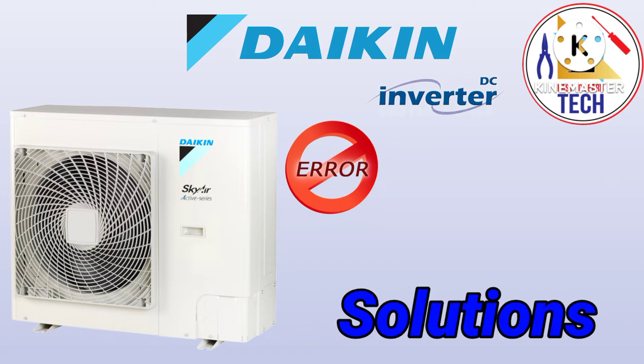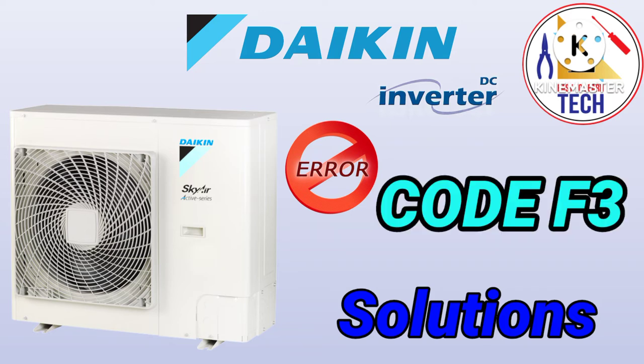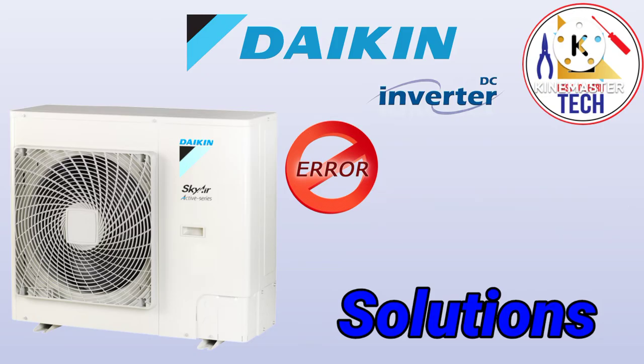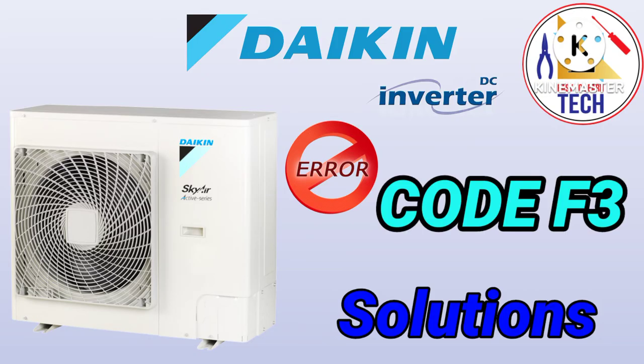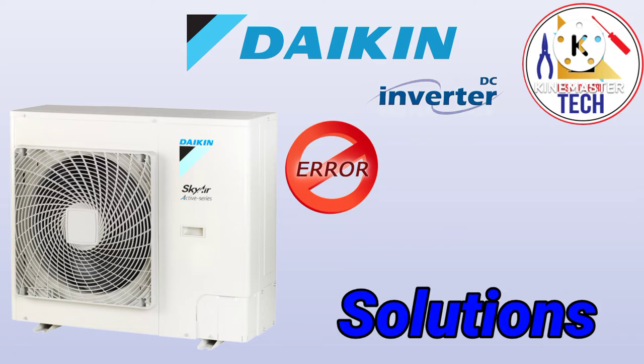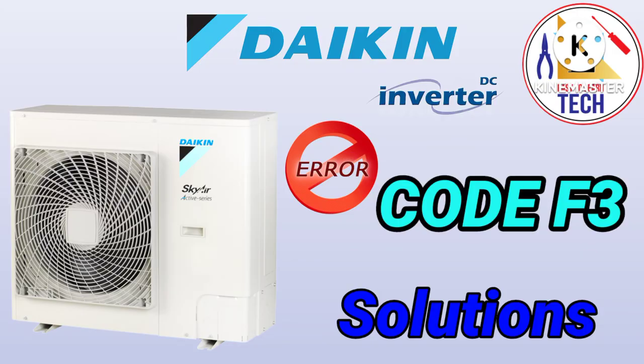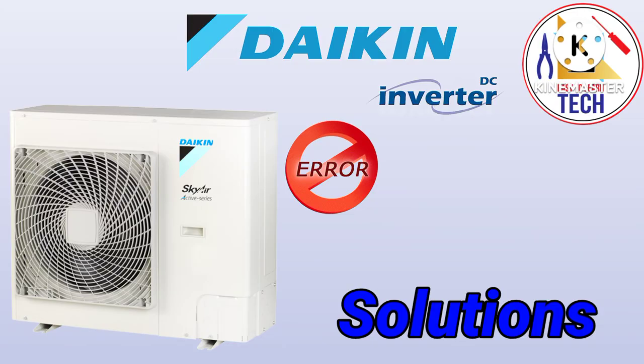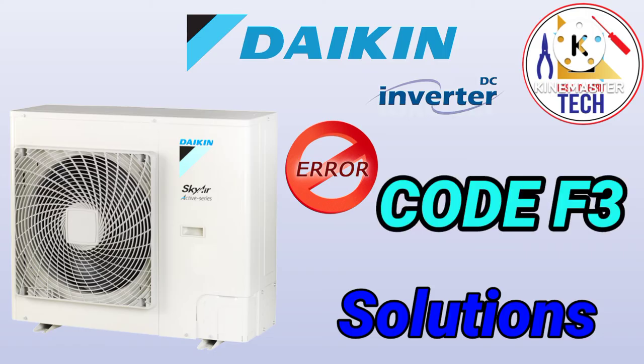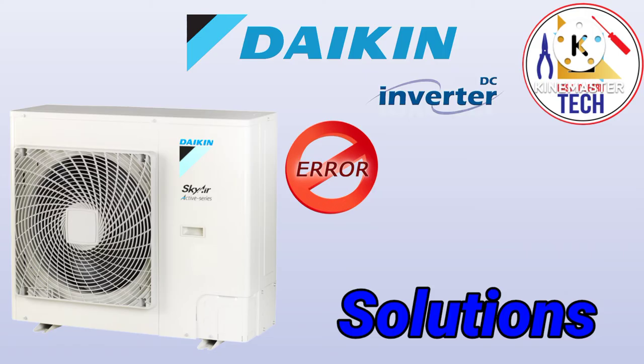What are the causes for the error F3? The main cause is the condenser area being blocked with dust and dirt. If it is not clean, and our refrigerant cycle is not getting properly cooled down, at that time it will show the error F3. Second, if the piping is pinched or clogged in some area and the refrigerant is not flowing properly, at that time also you will get the error F3.